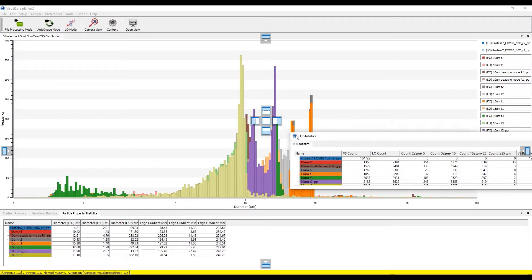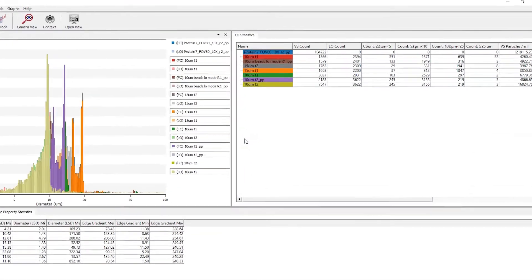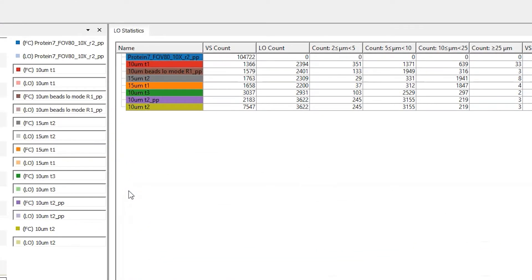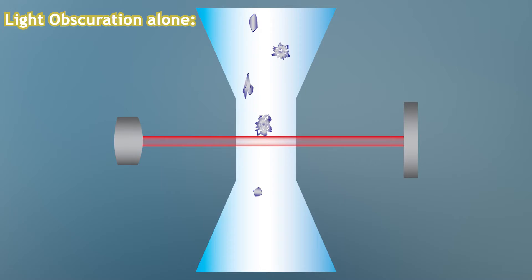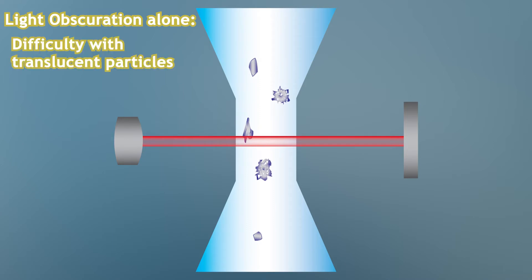Light obscuration continues to be the prevailing method in many industries by which particle size and concentration are analyzed. That being said, we know light obscuration has its drawbacks. LO can have difficulty recognizing and registering translucent particles like proteins, given their index of refraction is often nearly identical to that of the carrier fluid.